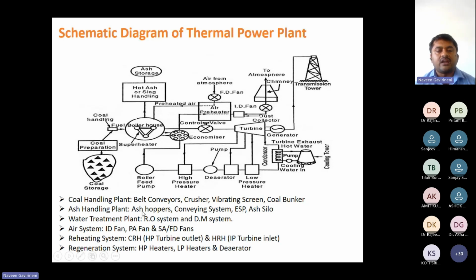Whereas the ash handling plant is for the output. That means after burning of the coal, the flue gas goes through the chimney. In between, we have an ESP arrangement. Why do we have it? There are limitations from the pollution control department, not only in Andhra, in every state. It is SOx, NOx, and SPM. SPM should be maintained less than 50 ppm. Earlier it was 50 ppm; now, as per the norms, it comes down to 30 ppm only.